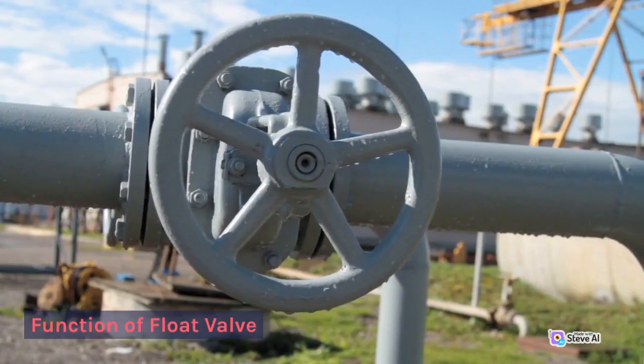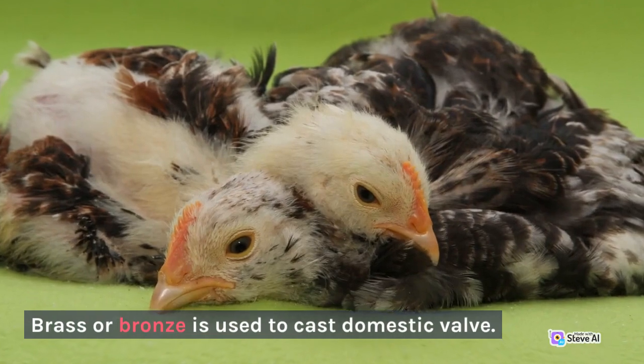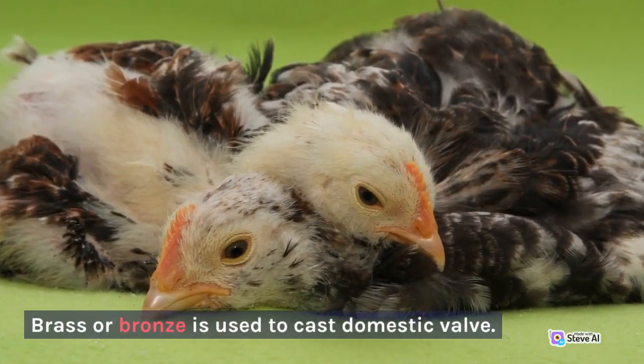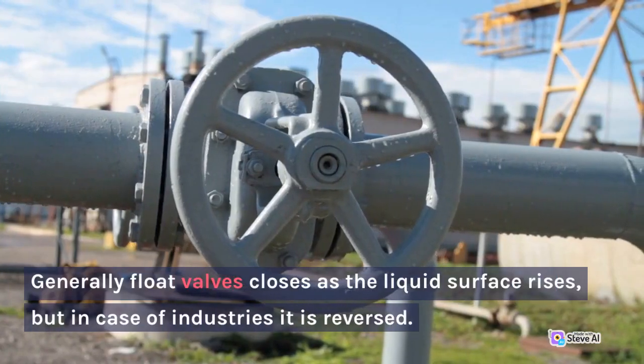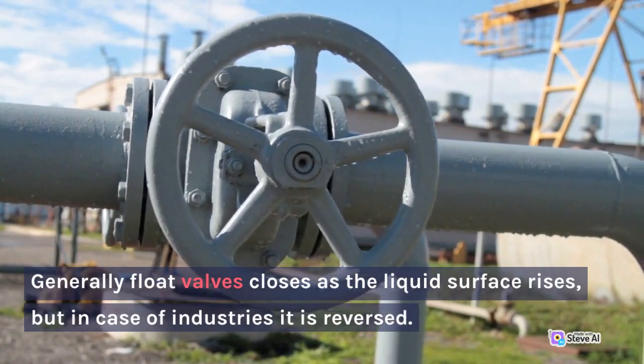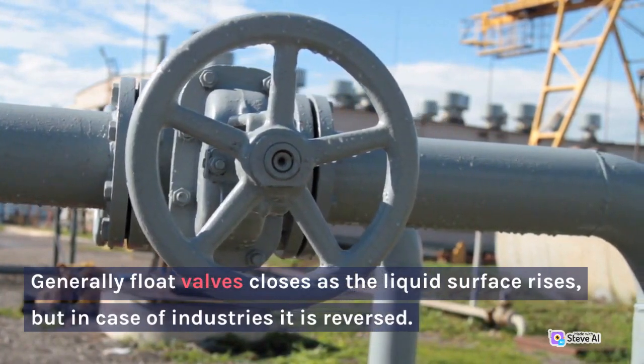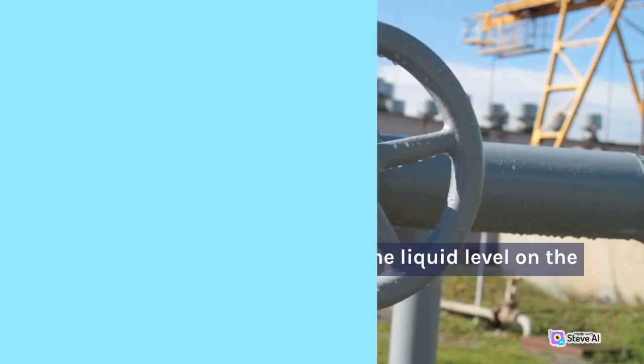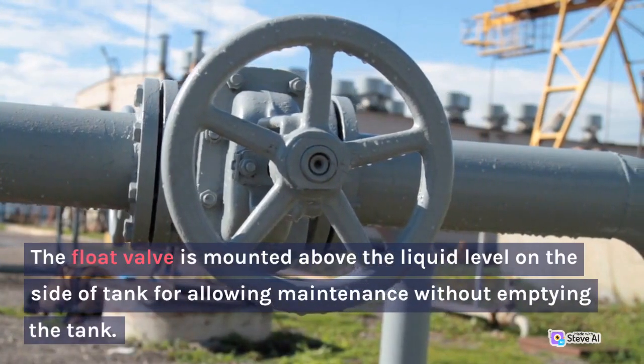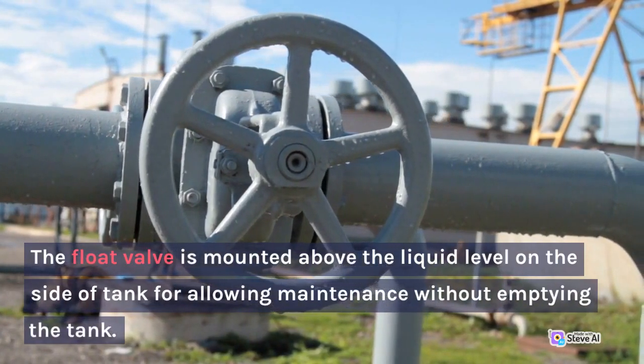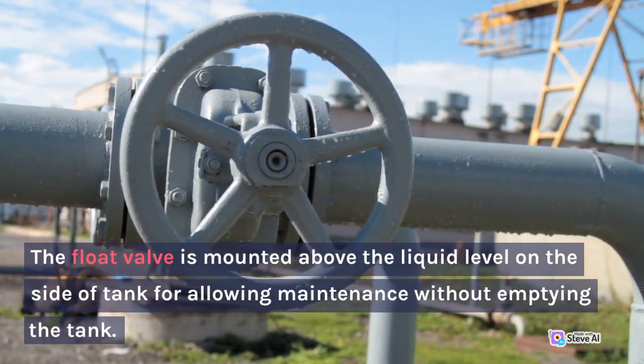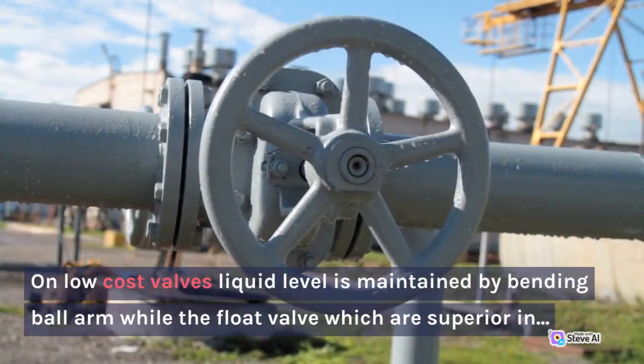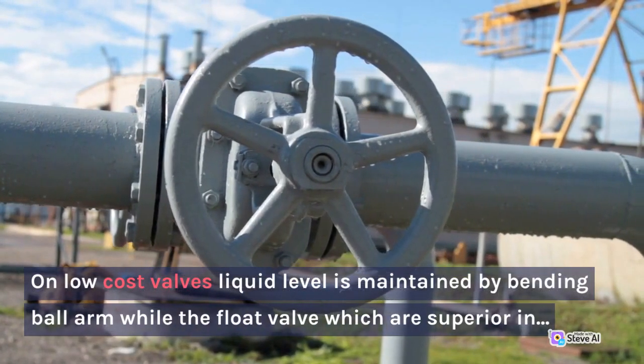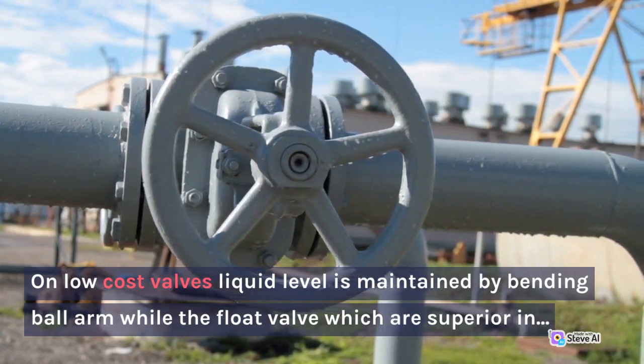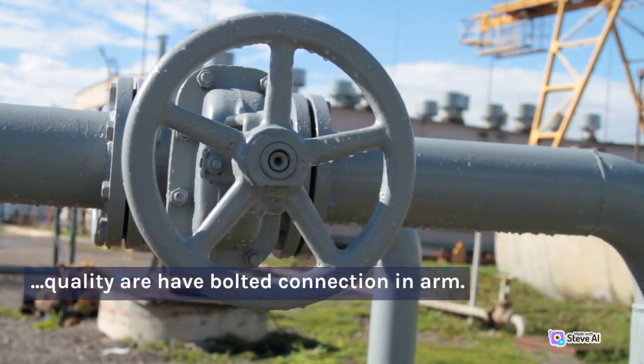Function of float valve. Brass or bronze is used to cast domestic valves. Generally, float valves close as the liquid surface rises, but in industries it is reversed. The float valve is mounted above the liquid level on the side of the tank for allowing maintenance without emptying the tank. On low-cost valves, the liquid level is maintained by bending the ball arm, while the float valves which are superior in quality have a bolted connection arm.